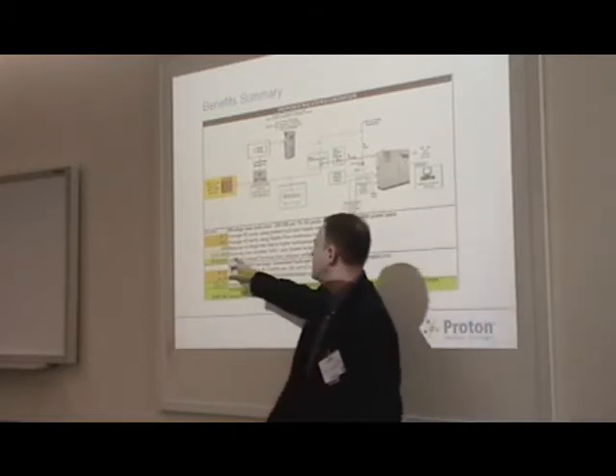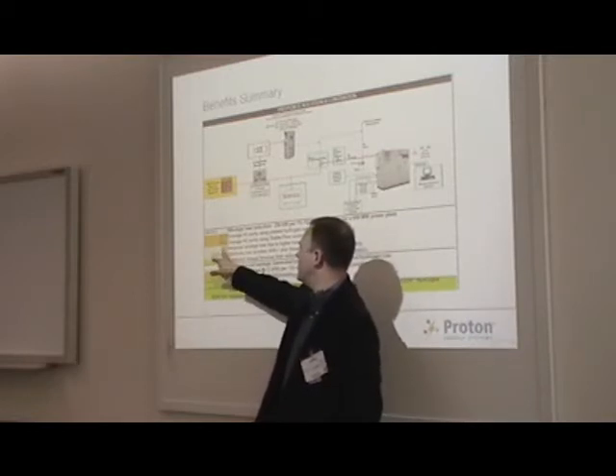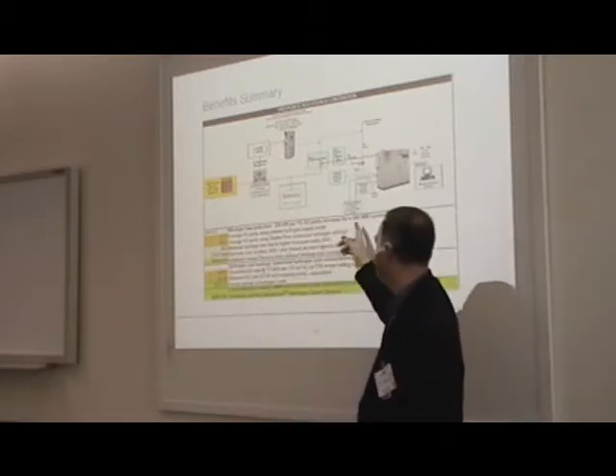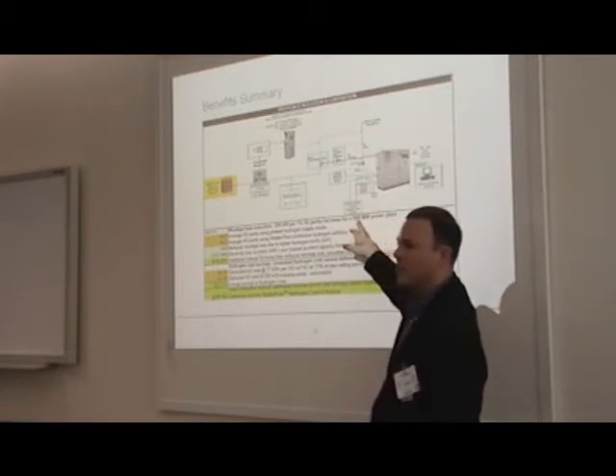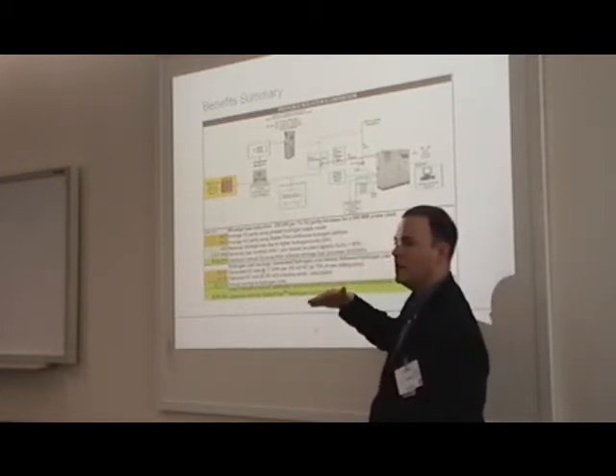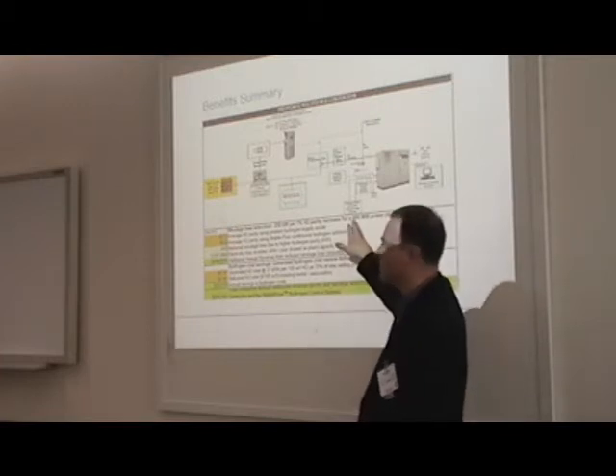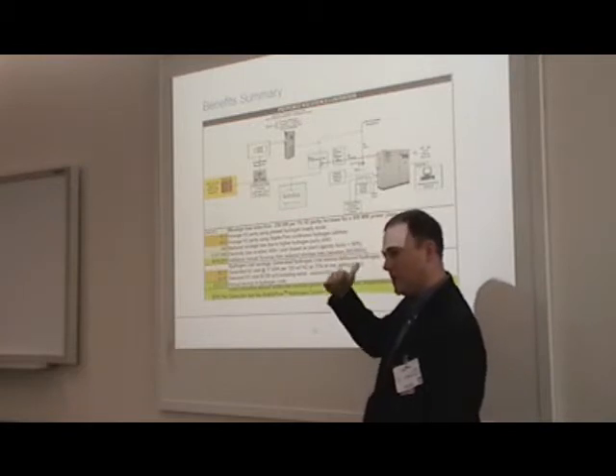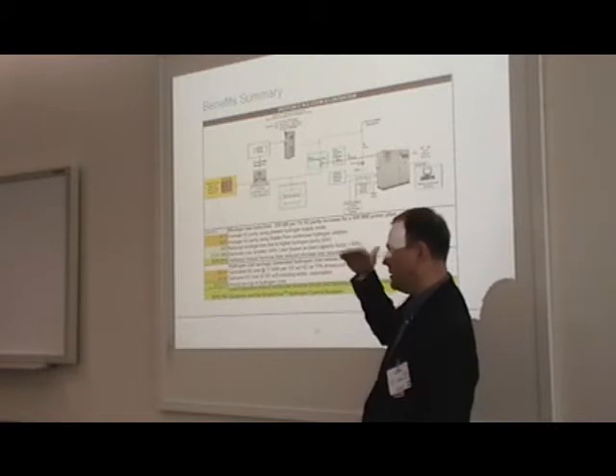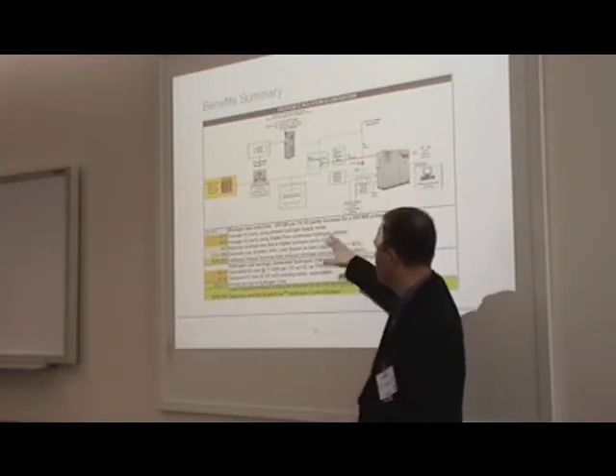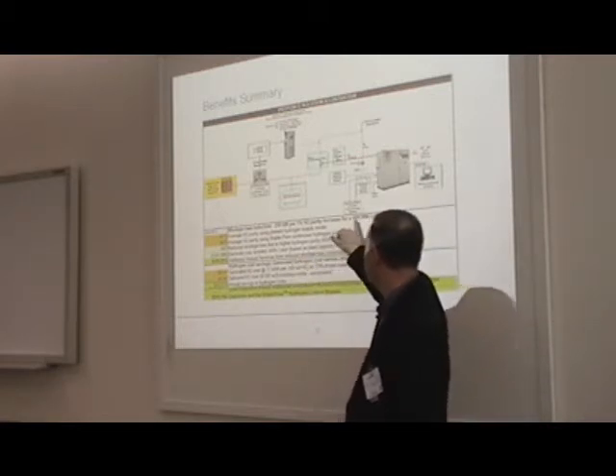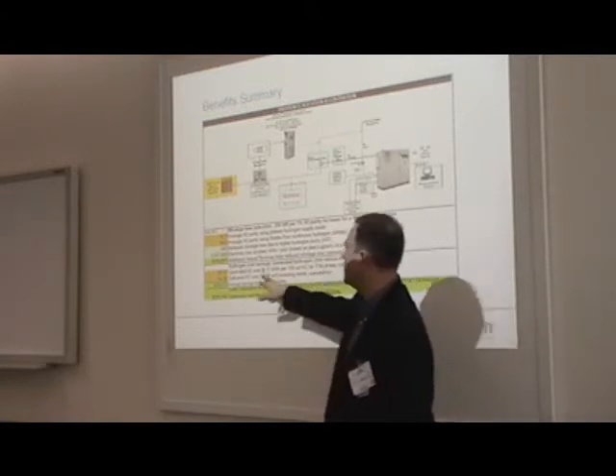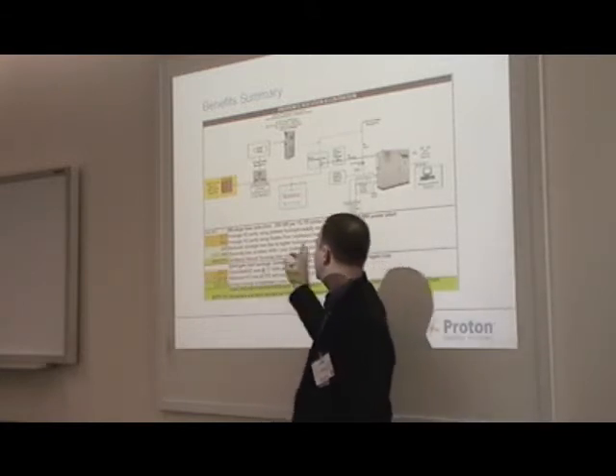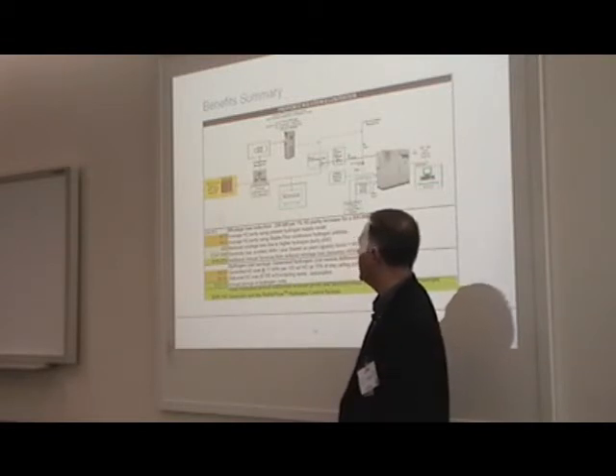Now you'll say, well, you were saying 250 kilowatts per percent, that doesn't add up. Well, in our calculations, we take into account if your generator is not at 600 megawatts. That 250 kilowatt per percent savings was based on a 600 megawatt plant. So if your plant's 400 megawatts, then the 250 comes down a little bit. If you're a 250 megawatt CT plant, that comes down more. So it's ratioed based on the size of the electric generator, just so you're aware of that. So in this case, it was 450 kilowatt savings based on hydrogen purity alone.